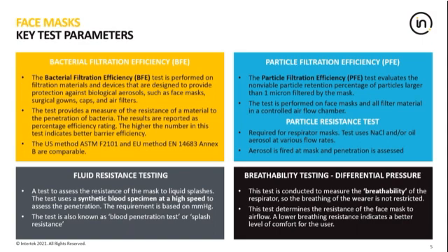The next test is fluid resistance testing. This can also be known as blood penetration or splash resistance test. The object of this test is to determine the resistance of the mask to liquid splashes, such as blood and other bodily fluids. During the test, a high velocity sample of synthetic blood is effectively fired at the mask, and this determines the pressure at which it will penetrate the mask. And it is the pressure then which is reported as the final test result.